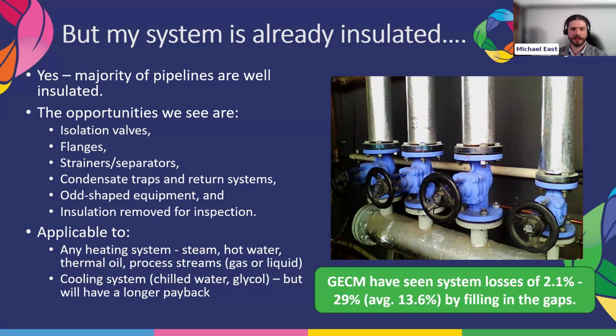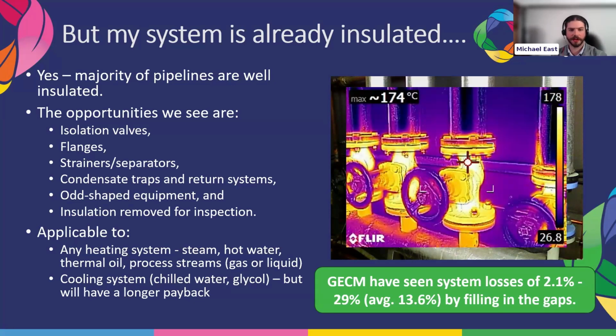So what you can see here in the picture is a fairly common steam manifold, nicely insulated pipes on top. But when we look at that with the thermal imaging camera, you can see those valves at 174 degrees - very obvious that there's a lot of heat coming from those.